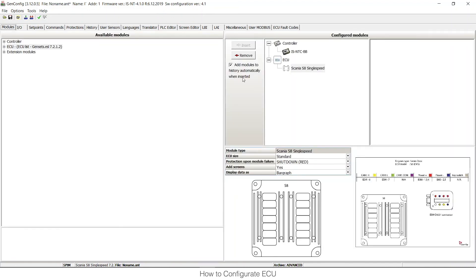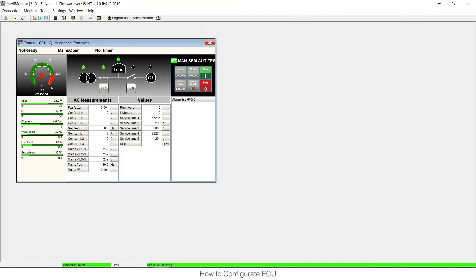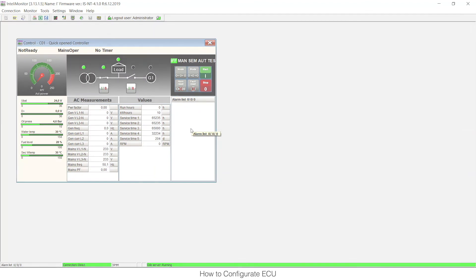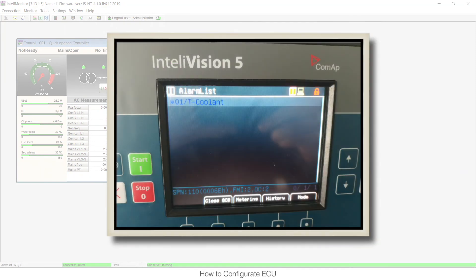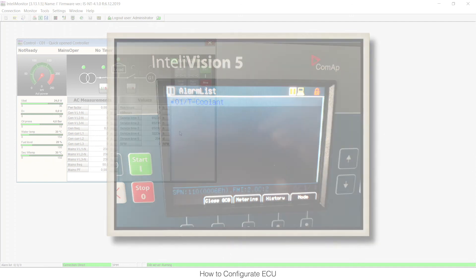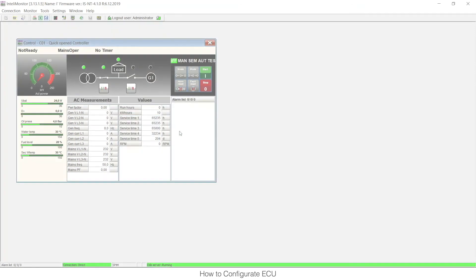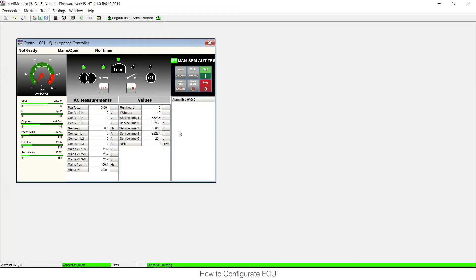So this is how to set it up. Then of course as in GenConfig always you need to write it into the unit using this red button. And then if it is properly configured and if there is any alarm from the ECU, you would see it in the alarm list with blue background. Also on the display. So this was how to find the information, how to configure it, what will it do when there is an alarm.